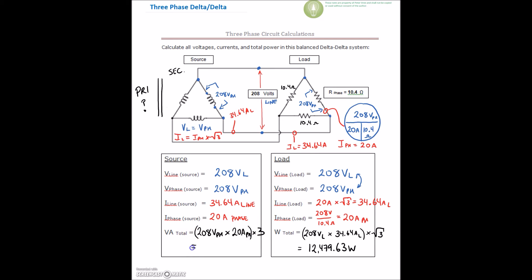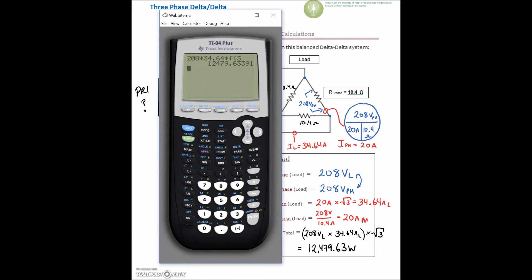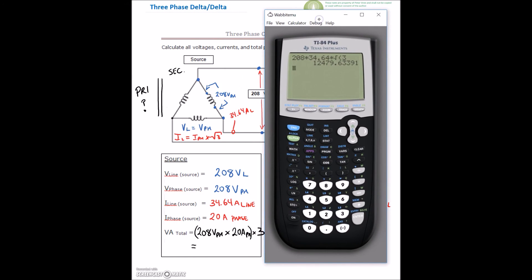And we should find that that comes to a value that's very close. So that's probably going to be 12,480. Let's check. So we've got 208 volts. We're going to multiply that by 20 amps on the phase. Then we've got three phases, and we've got 12,480.